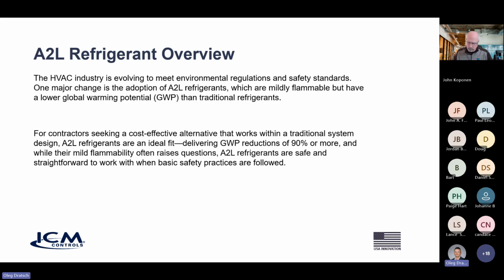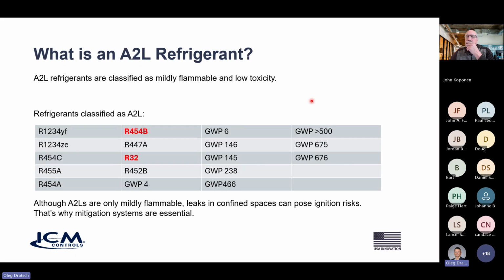And so when you think about those refrigerants in a closed loop system for residential or commercial HVAC, any type of leak in that system could really pose a problem. So the role of A2L sensing and mitigation is to sense for those A2L leaks and then perform mitigation tasks within the HVAC system. The refrigerants that I'm referring to today are the R454B and R32 refrigerants. Those are the predominant refrigerants in HVAC systems today. This is what the industry is shifting to, and this is what you'll see out in the field today.